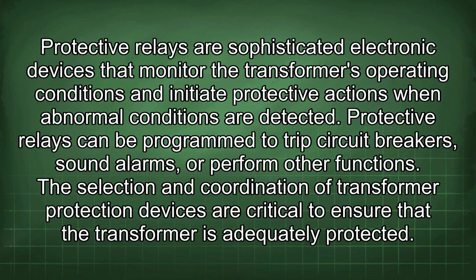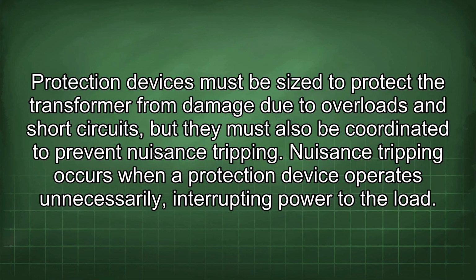Protective relays are sophisticated electronic devices that monitor the transformer's operating conditions and initiate protective actions when abnormal conditions are detected. Protective relays can be programmed to trip circuit breakers, sound alarms, or perform other functions. The selection and coordination of transformer protection devices are critical to ensure that the transformer is adequately protected. Protection devices must be sized to protect the transformer from damage due to overloads and short circuits, but they must also be coordinated to prevent nuisance tripping.